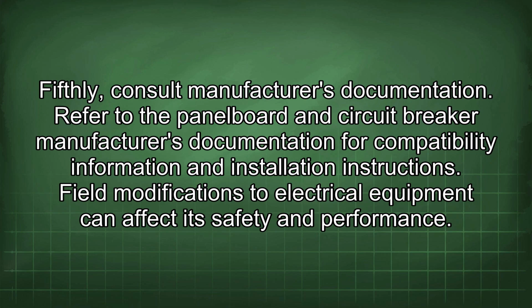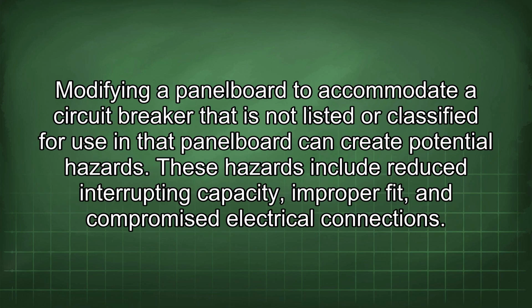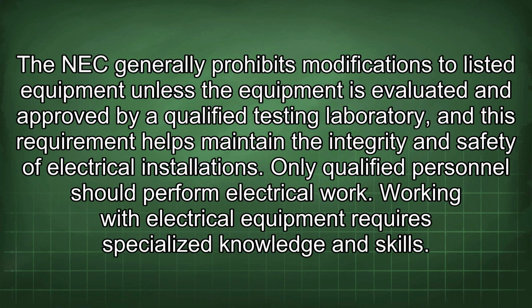Field modifications to electrical equipment can affect its safety and performance. Modifying a panelboard to accommodate a circuit breaker that is not listed or classified for use in that panelboard can create potential hazards. These hazards include reduced interrupting capacity, improper fit, and compromised electrical connections. The NEC generally prohibits modifications to listed equipment unless the equipment is evaluated and approved by a qualified testing laboratory, and this requirement helps maintain the integrity and safety of electrical installations.